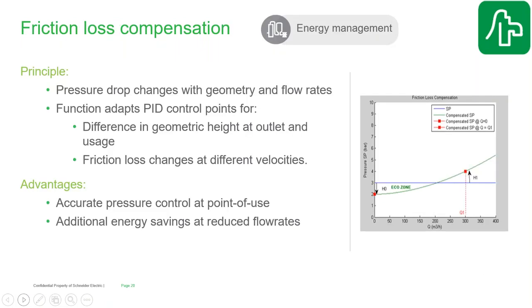But in addition to just energy monitoring and analysis, there are also functions inside the intelligent drives of today to try and improve the efficiency. An example of this would be what we call the friction loss compensation function. It sounds a little complex, but what it does is enable the drive to adapt the output pressure from the pumps according to the variable flow rates. The idea behind this is if you have higher flow rates, you will have a higher pressure drop through your piping system between the pump and your sprinkler heads, so your pump output pressure needs to be higher at high flow rates in order to maintain the same pressure at the sprinkler head.